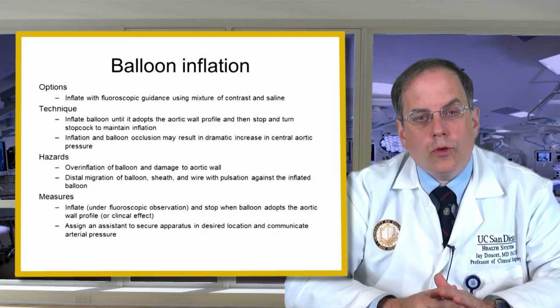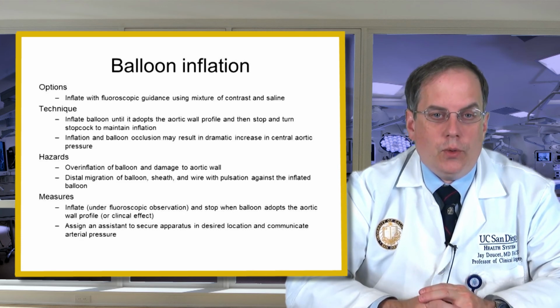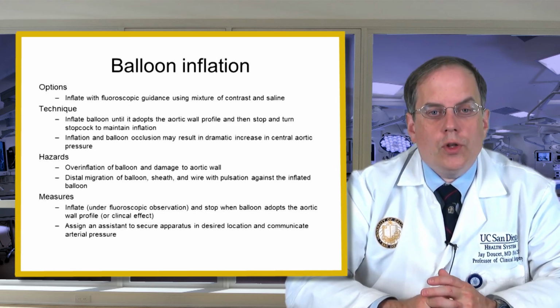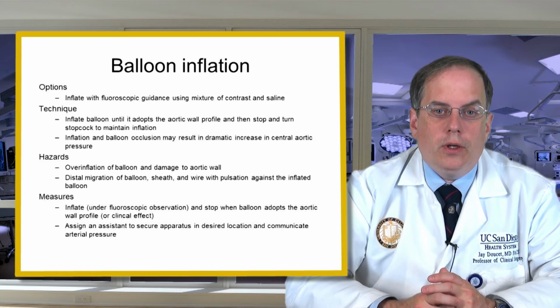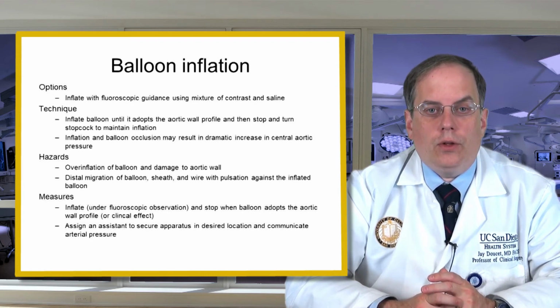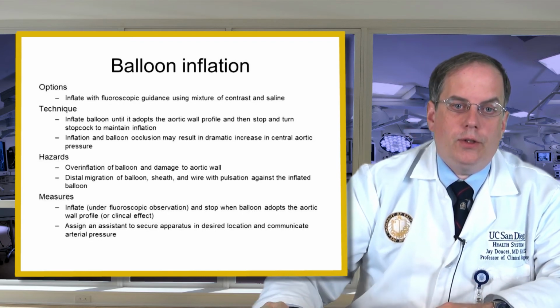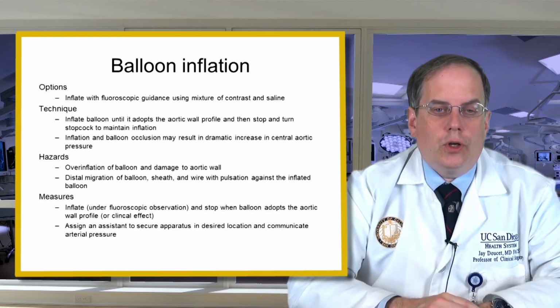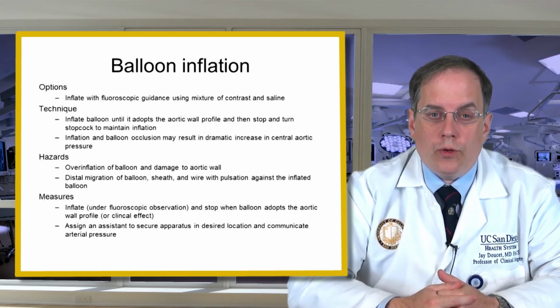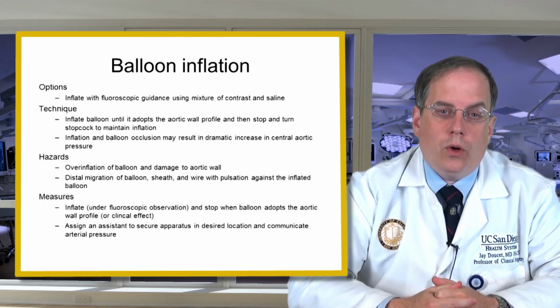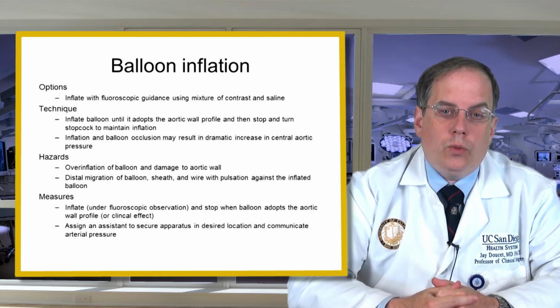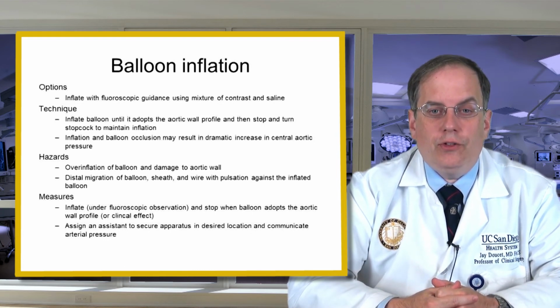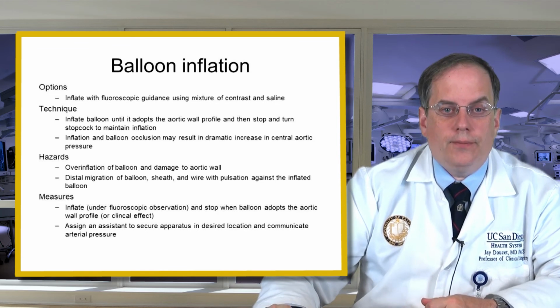It's important not to overinflate the balloon and cause any damage to the aortic wall, and we have to ensure that the balloon does not migrate distally or that it does not allow the sheath and wire to be pulled out against the inflated balloon. Hazards to look out for are that we do not overinflate the balloon and cause damage to the aortic wall, or that the balloon, sheath and wire do not become displaced distally due to pulsation.